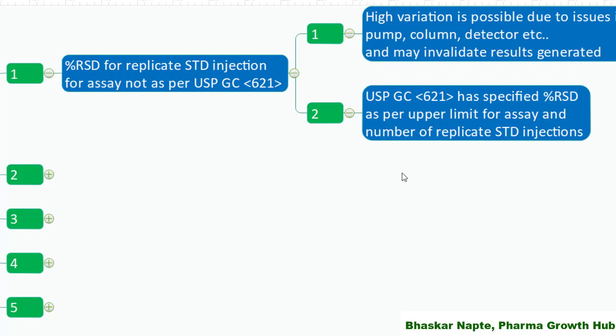High variation is possible due to issues in the pump, column, detector, etc., and may invalidate results. Setting a suitable percent RSD for replicate standard injections is very much needed. Refer to USP General Chapter 621 — based on your upper assay limit and number of replicate standard injections, you will be able to identify the appropriate percent RSD for your case.